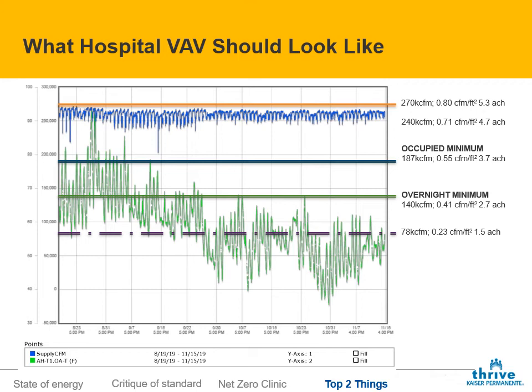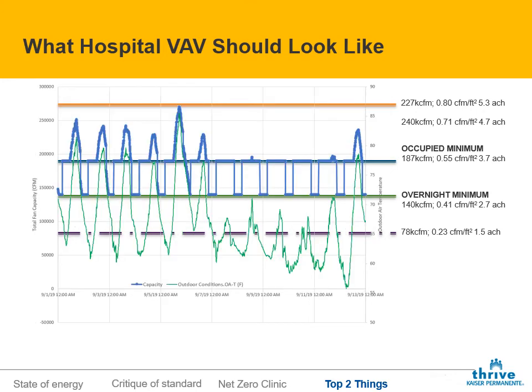Okay, so this is more of the range that we should be seeing in the VAV systems, right? Let's zoom in a little bit and show you what I think VAV should actually look like. Obviously, when it's really warm out, when it is 90 degrees, then we should be going up to the peak. But in the mild temperatures during the day, we should be dropping down to that occupied code minimum. On the overnight basis, we should be dropping down to that unoccupied code minimum. And we should be seeing this pretty routinely. And we can be very numeric about this when we do projects.